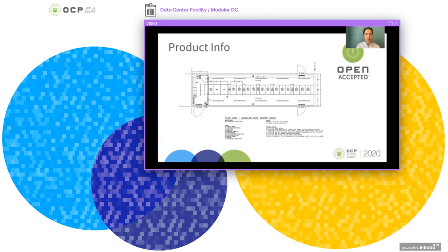This could also be used as a security measure, where if you had maintenance and you wanted to restrict access to certain components in the electrical lobby for certain employees or certain clearances, again, you could isolate the hot aisle and cold aisle as well. It also helps with environmental control by essentially creating a man trap in that area, and also reducing dust exposure.